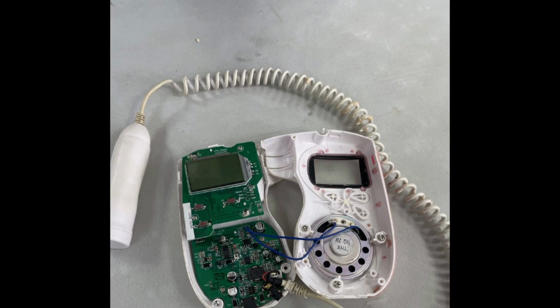Low sensitivity to motion of the fetal heart may be due to poor connectivity within the device. To investigate this, the device should be turned off and batteries should be removed for safety. The device can be opened up so that the circuit can be examined. You can begin investigating the connectivity using a multimeter and the continuity setting. Resolder the internal circuit where needed.